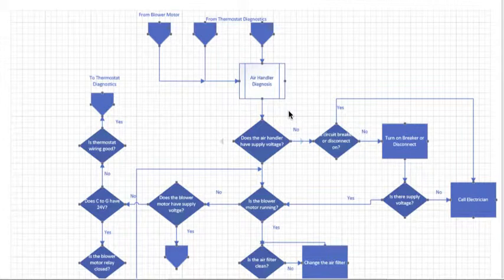So when we come into the air handler diagnostic procedure, we're either coming from thermostat diagnostics or from blower motor diagnostics, but we're starting off by checking and seeing if the air handler has supply voltage. If the air handler doesn't have supply voltage, you need to go check and see if the disconnect or breaker is on. If the breaker's off, you've got to turn it on or put the disconnect to the on position.